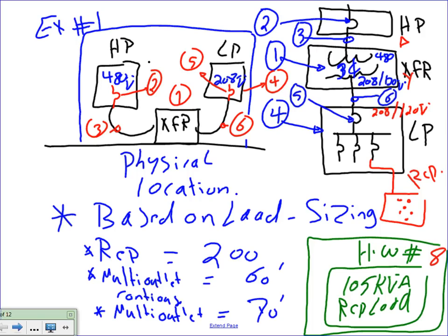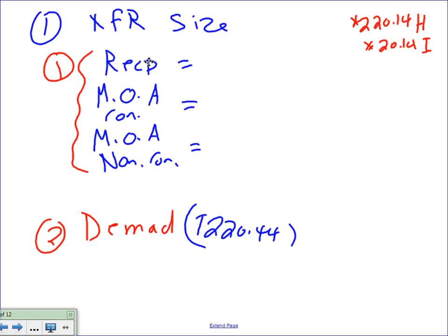Okay, let's go ahead and start. Now, I put 220.14(H) and 220.14(I). These are the code sections. From 220.14(H) and 220.14(I), Chris is going to go check them for me. You're going to do the calculation on the receptacles. It will tell you, guys, in a commercial or industrial building, every receptacle is assumed to be at how many volt-amps?